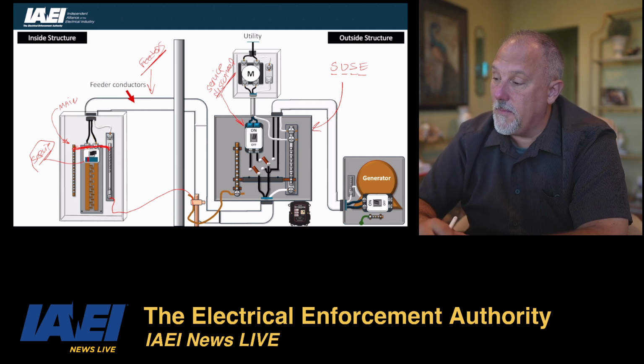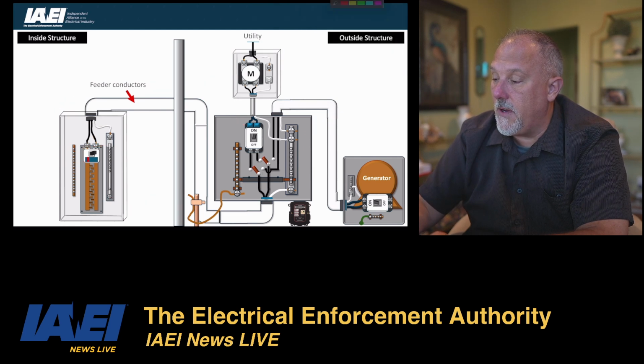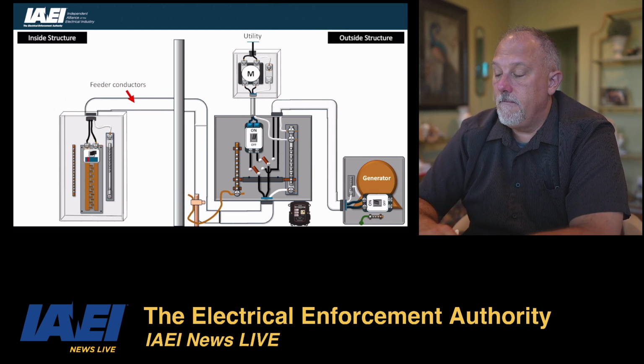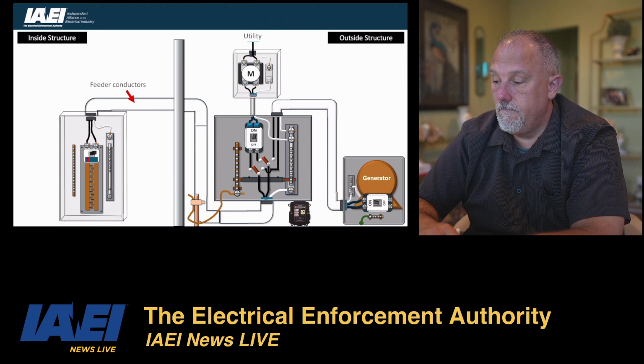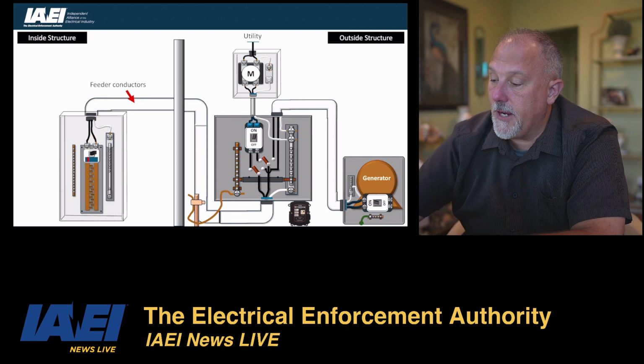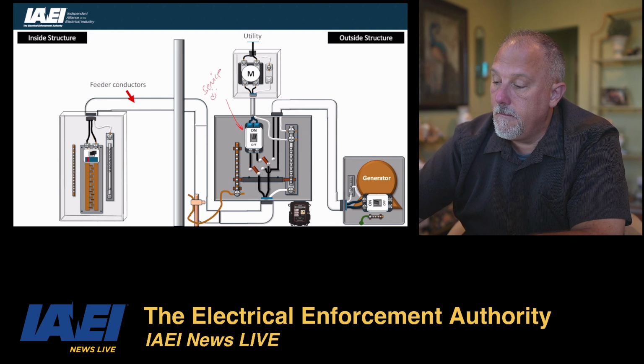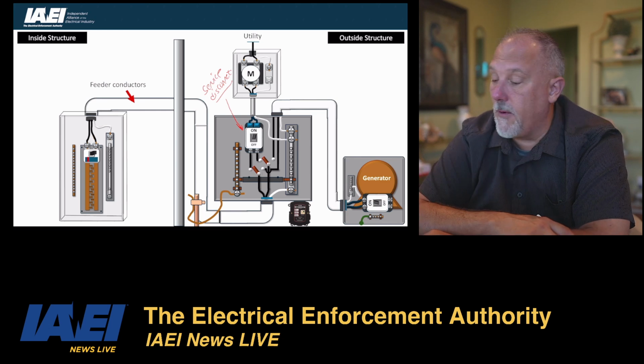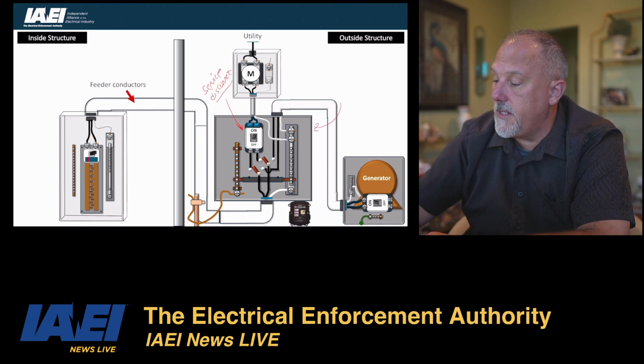So I'm going to stick with my last discussion point. It looks, if I'm following the NEC, if I'm following the letter of the code, that is this breaker that's in this transfer switch. This breaker is the service disconnect. That's your service disconnecting means. There's no way around that. This is going to have to be service equipment.